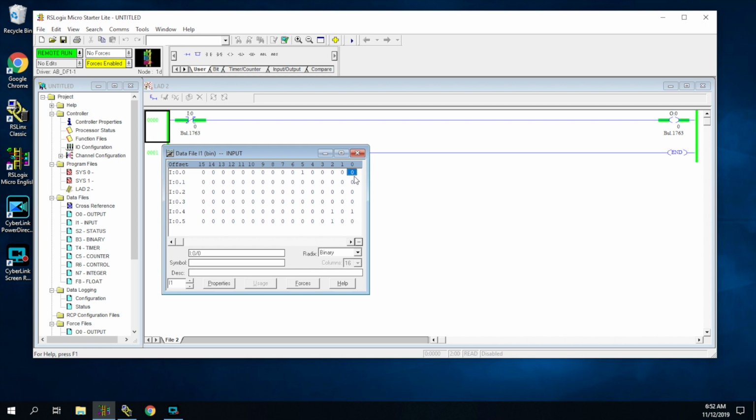The other one is if you hook a normally closed button up to this instruction, there will be power running through it at all times, or running to the terminal at all times. Meaning that when you don't press the button, it will have 24 volts at the terminal, okay? So just when you're setting stuff up, you're going to see that normally closed buttons are going to be used a little bit differently. So kind of think about that.